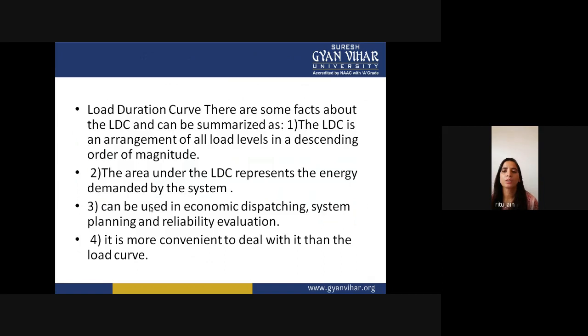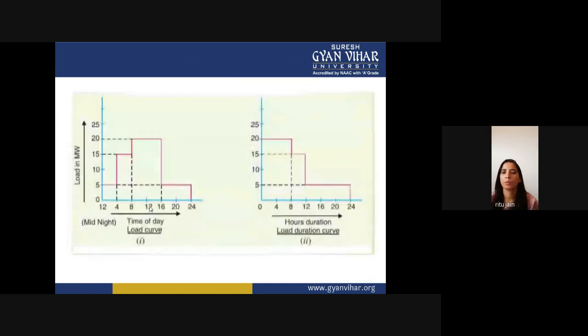The area under the LDC represents the energy demanded by the system. It can be used in economic dispatching, system planning, and reliability evaluation. It is more convenient to deal with than the load curve. From the diagram, you can see that this is your load curve and this is your load duration curve.